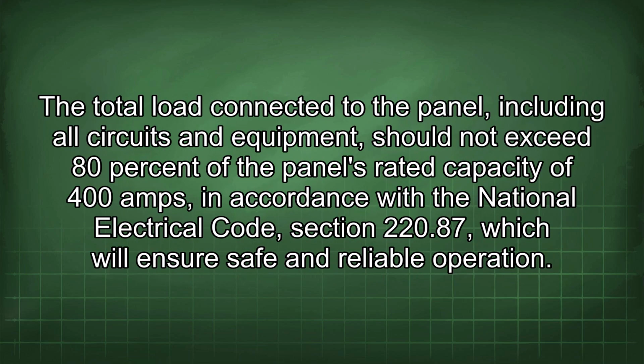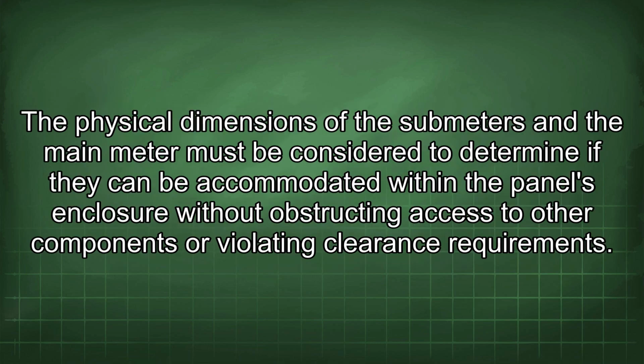The total load connected to the panel, including all circuits and equipment, should not exceed 80% of the panel's rated capacity of 400 amps, in accordance with the National Electrical Code, Section 220.87, which will ensure safe and reliable operation. The physical dimensions of the submeters and the main meter must be considered to determine if they can be accommodated within the panel's enclosure without obstructing access to other components or violating clearance requirements.